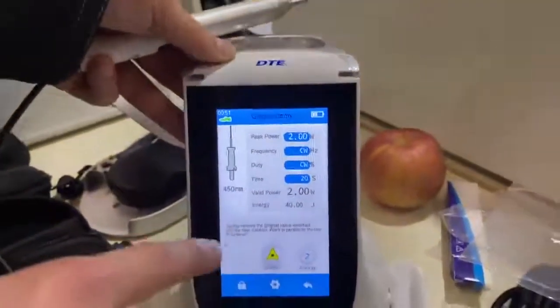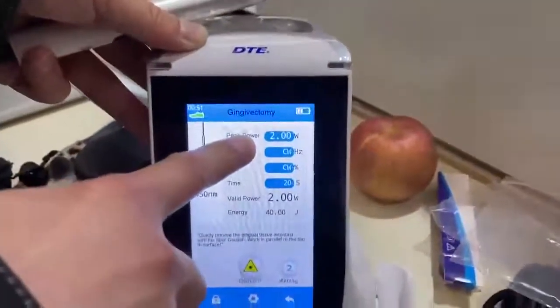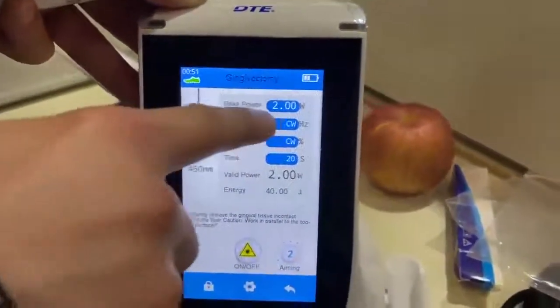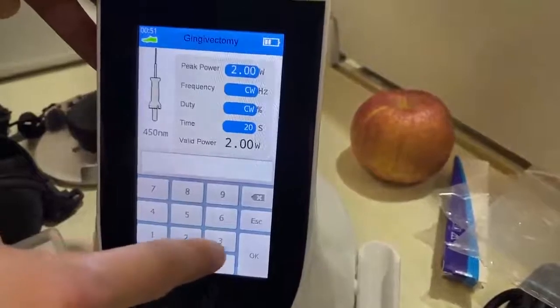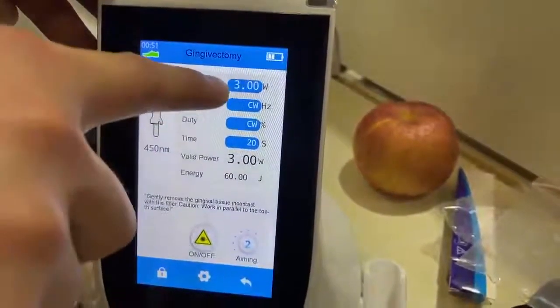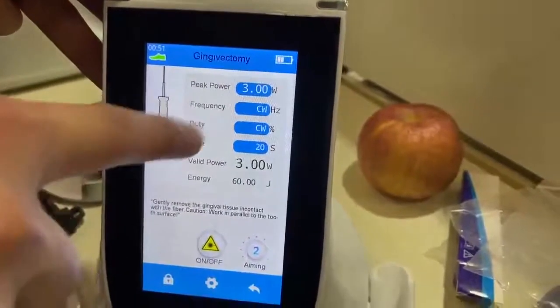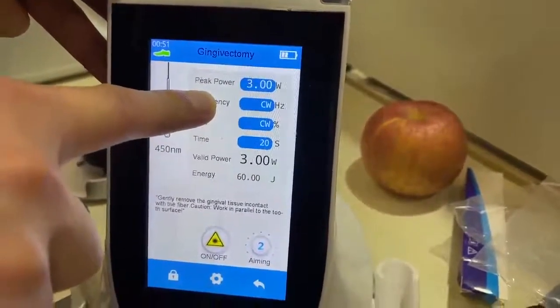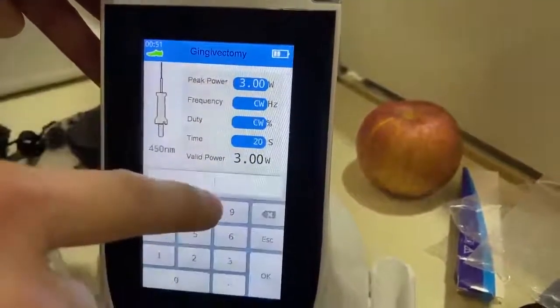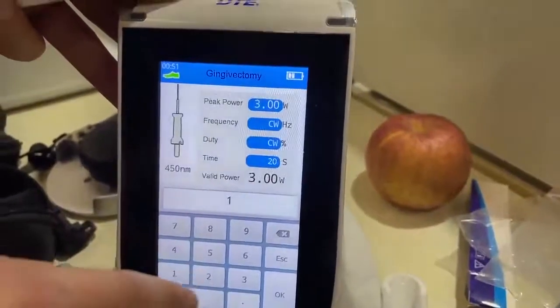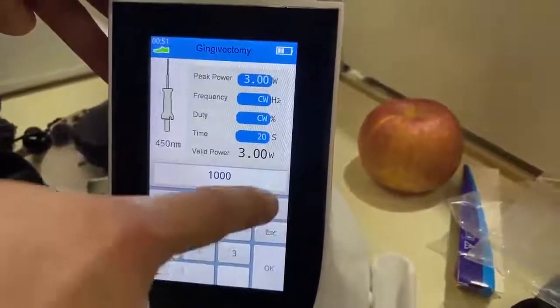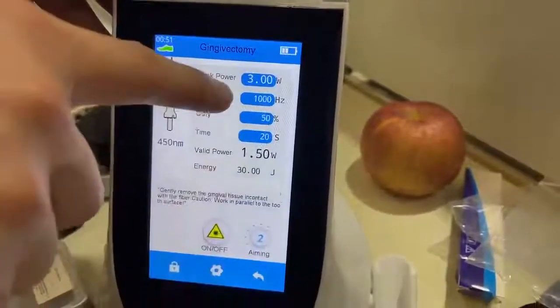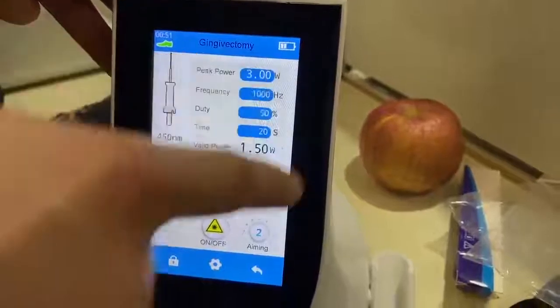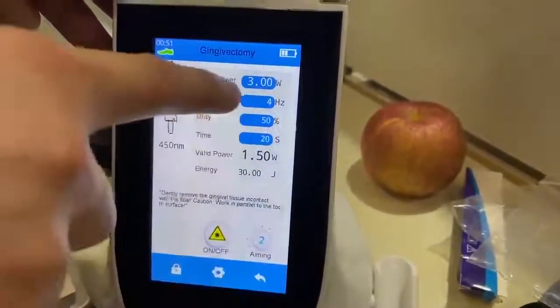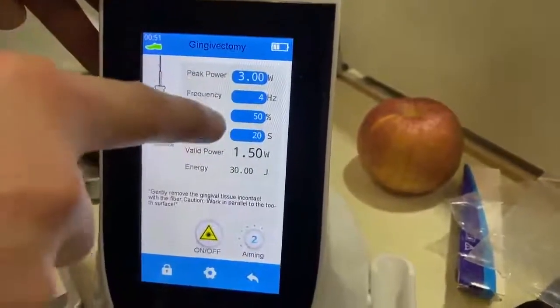But sometimes if you think the power is not enough, you can also change the power. Like this, if you think 2 watts is not enough, you can touch the 2 watts, and then we can press 3 watts and okay. So now it's 3 watts, right? So you can change it if you want. And for frequency, if you don't want the continuous mode and want to use the pulse mode, you can change the frequency. For example, 1000 frequency, you can see 1000 frequency, right? And also you can change it to 4, the frequency is 4 hertz. So you can also change the frequency, and the duty you can also change.